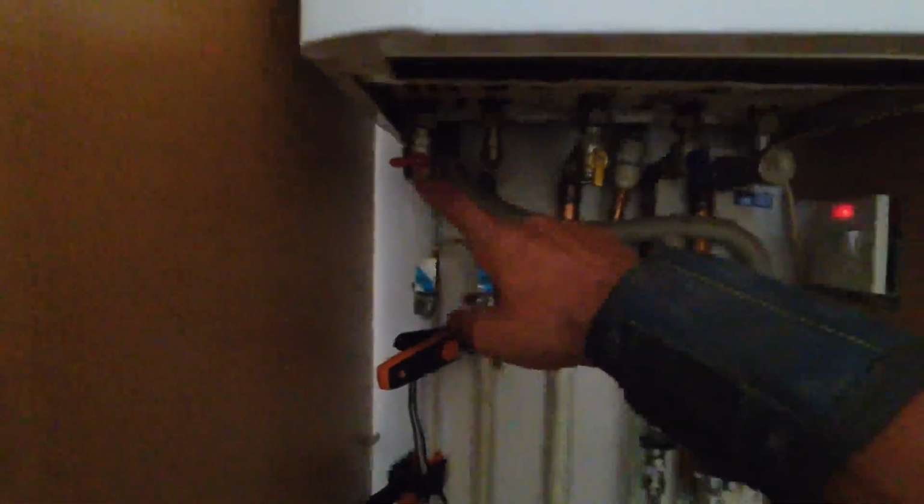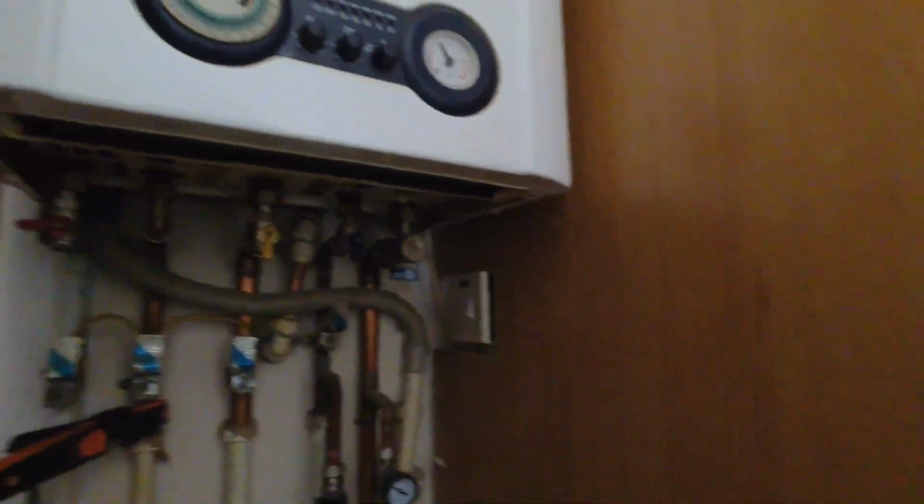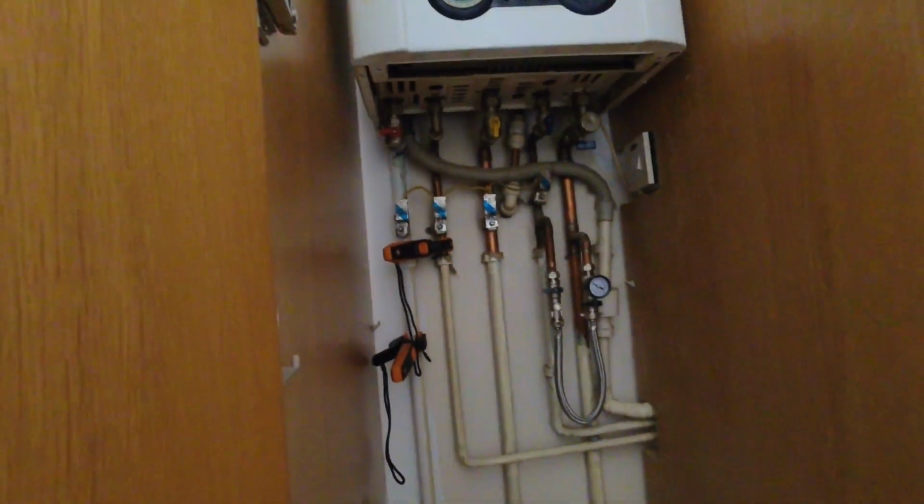Right, this is the one, Heatline Vizo. Got hot tap running at the moment. Just got the temperature clamps on there. I have isolated the flow and returns now, but you can see on here, the top one is the flow clamp, and that's already hit 53 degrees. And it's climbing a little bit slower now because I've isolated it, but that was on about 20 degrees when I first put it on. And it shot up, so definitely diverter valve. We are now going to kill the power, let the boiler run cold, and then get the diverter valve swapped out.